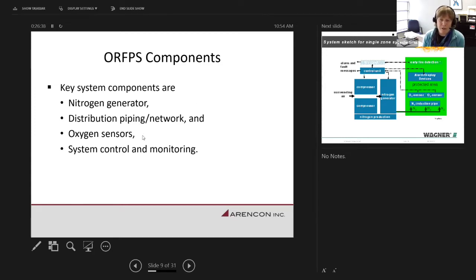Absolutely key on this is that we need the oxygen sensors. They are located throughout the protected area and distributed at floor level, at a high level, and through the midpoints. Again, thinking of a warehouse, but even if it was another room, you would have a blend of them. The numbers and locations of the oxygen sensors have been established within the norms and the standards in Europe. So the larger the space, the more sensors.